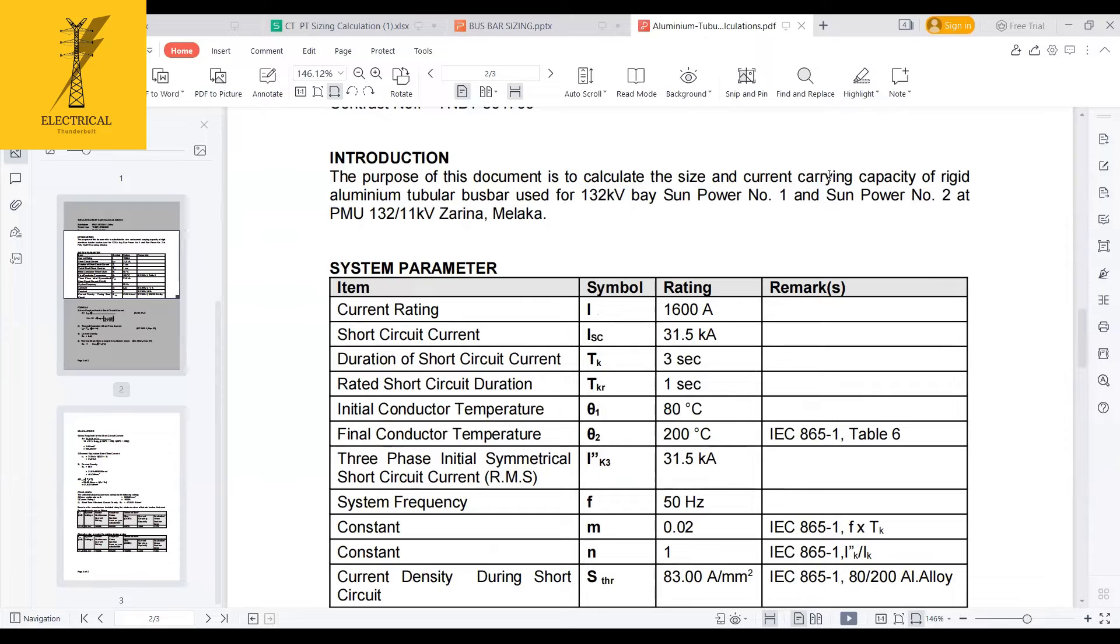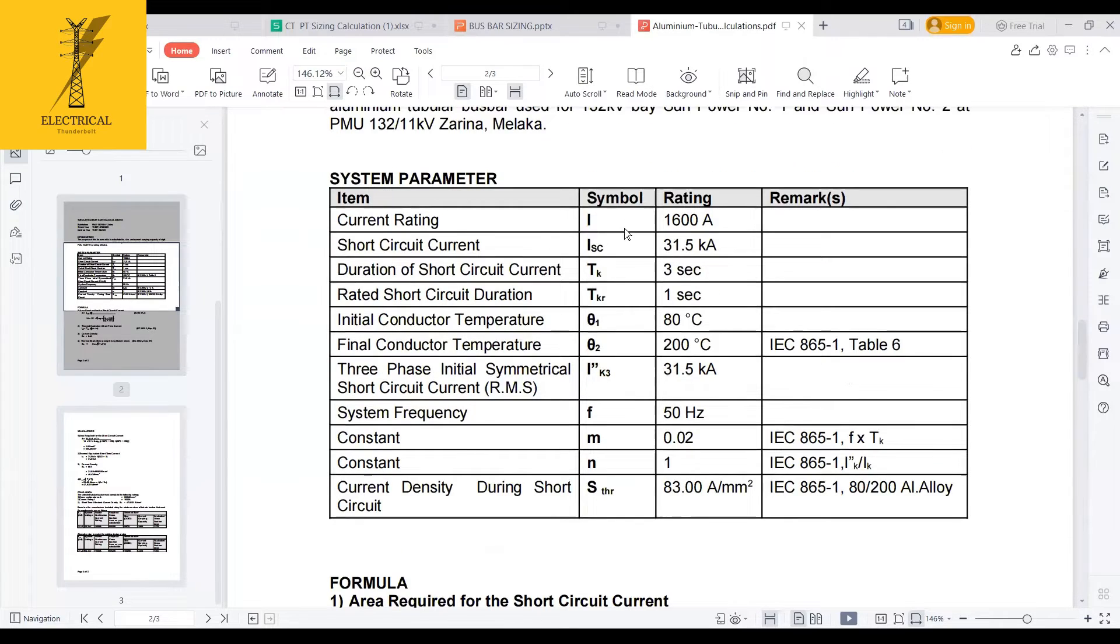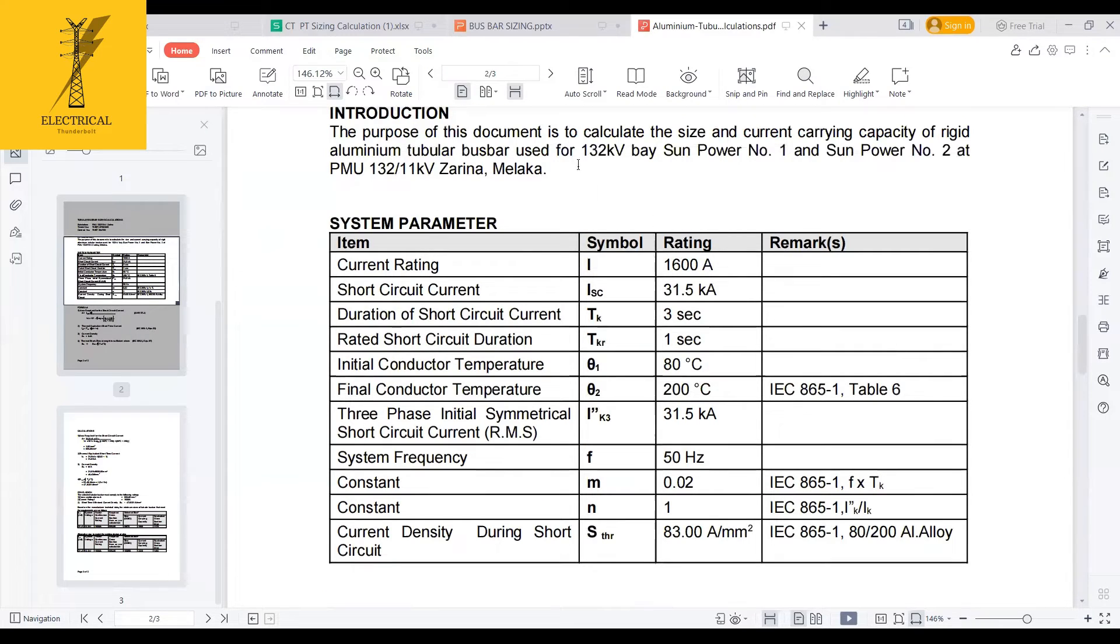They are not doing all the short circuit force calculation, winds, everything. But the way of doing rigid busbar is that. See here, this is one of the projects we have done. The current rating is 1600 amps, the short circuit current for 132 kV is 31.5 kA. And the duration of short circuit current is 3 seconds. And rated short circuit duration is 1 second. Initial conductor temperature is 80 degrees. And finally, it is 200 degrees, which I extracted from IEC 865-1 table 6. I will share you this document also.